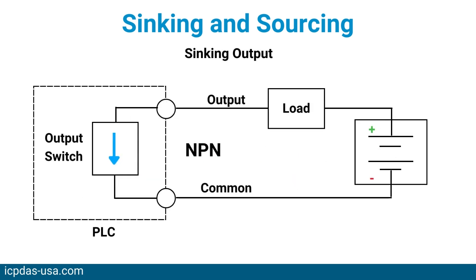The device's output signal does not provide power. It must be connected to a device that provides power for the output signal, or a sinking input with a loop power supply in the circuit.